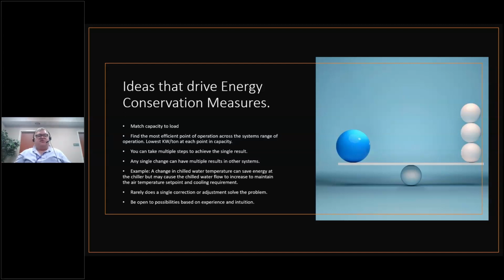A change in chilled water temperature can save energy at the chiller, but it may cause the chilled water flow to increase to maintain the air temperature set point and the cooling requirement. So I've changed energy used at the chiller for energy I'm now having to use at the pump. Is it the same? Can I actually get away with this? But that's something you have to keep track of. If I make a change here, how does it affect somewhere else?